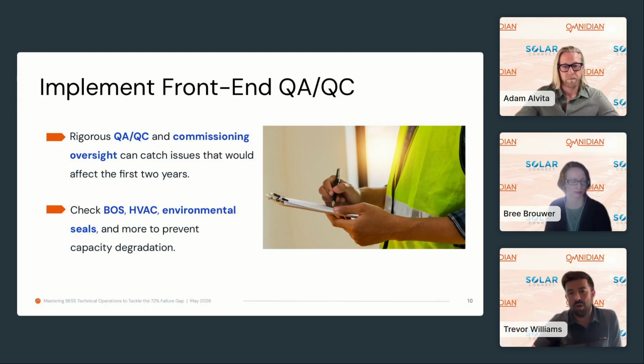I'll take it. It can be a combination of both, depending on the design of the system. I've seen self-contained systems, containers where there's an HVAC system for each container, and then some where that container is also inside of a building. I've also seen racks inside of a building with no self-contained systems, but they break it up so that there's no thermal event runaway, and also for fire suppression. So they try to isolate it so that if there is an event, it doesn't destroy the entire system, and they can try to compartmentalize it within the system.